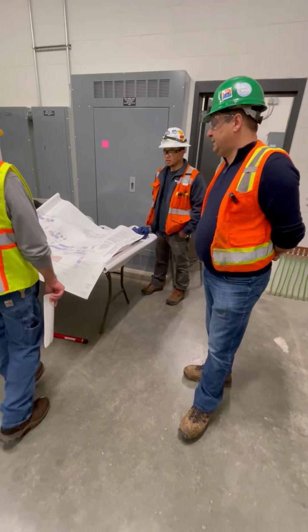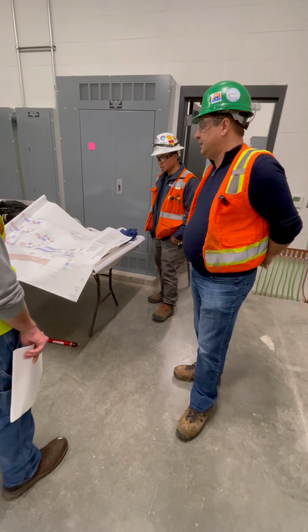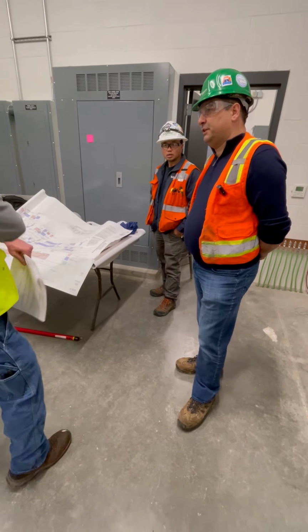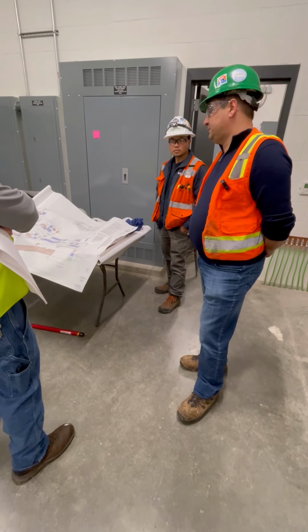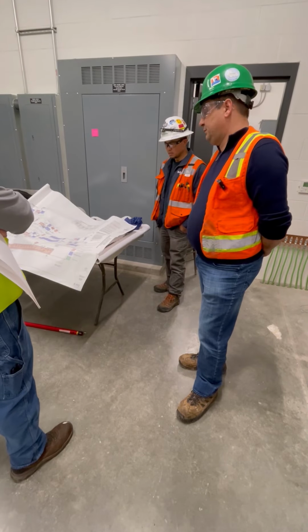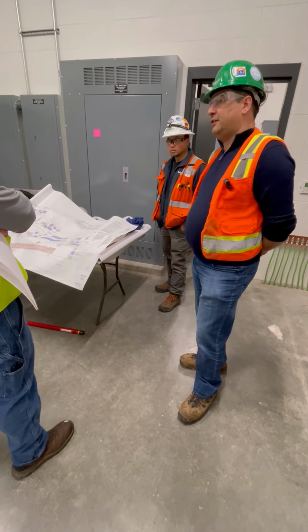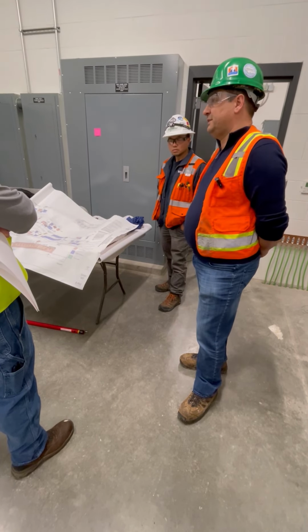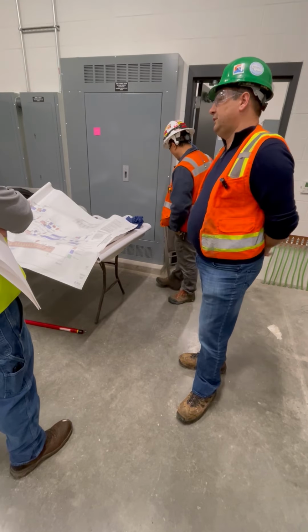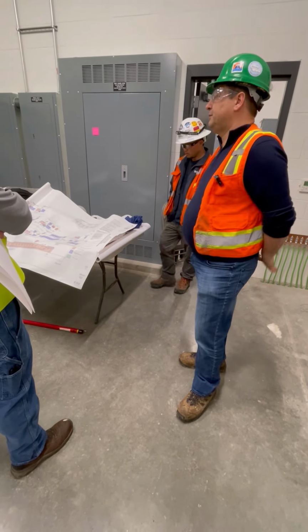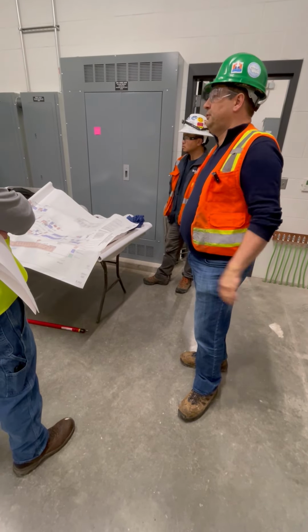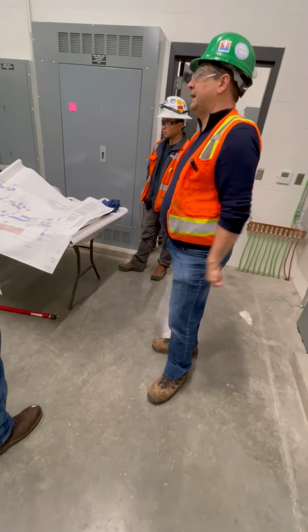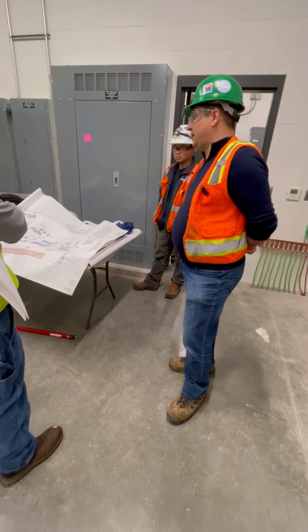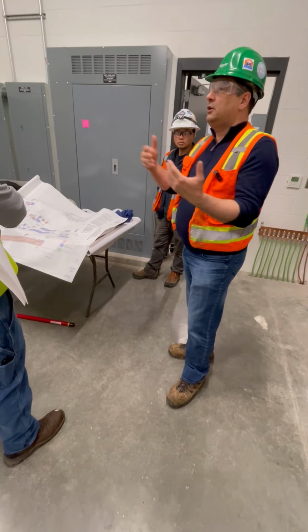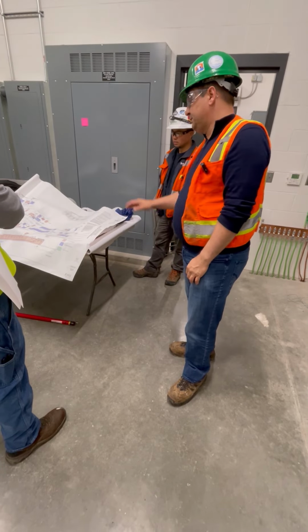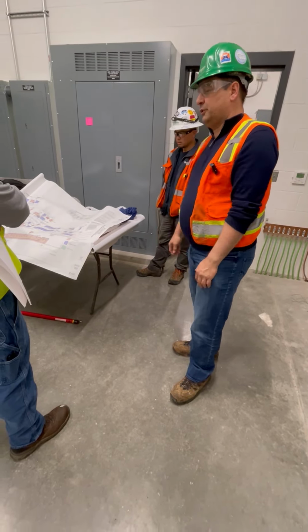One other thing to add, since we're talking about arc flash and one-lines: as he mentioned before, if there are any changes taking place, you have to update the documents. But also, NFPA requires the arc flash study be updated every 5 years to stay in compliance. If it's not updated, you could be fined if something happens, because you're not keeping the records current. Same thing with these records: if you have electricians or even us come on site and they're not accurate, you are responsible for providing all accurate documents. That's why the O&M manuals and one-lines are really important.